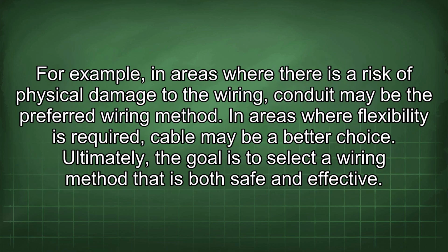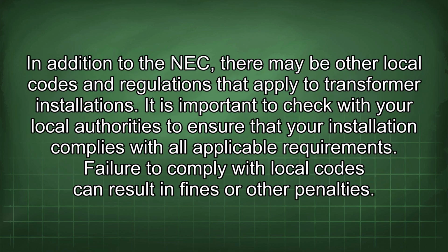For example, in areas where there is a risk of physical damage to the wiring, conduit may be the preferred wiring method. In areas where flexibility is required, cable may be a better choice. Ultimately, the goal is to select a wiring method that is both safe and effective. In addition to the NEC, there may be other local codes and regulations that apply to transformer installations. It is important to check with your local authorities to ensure that your installation complies with all applicable requirements. Failure to comply with local codes can result in fines or other penalties.